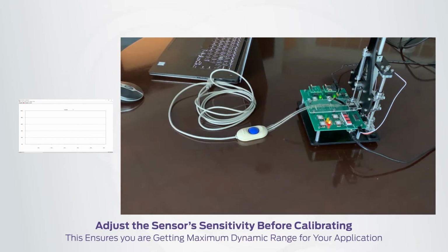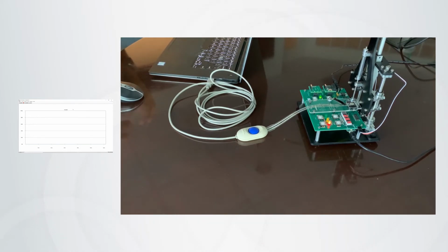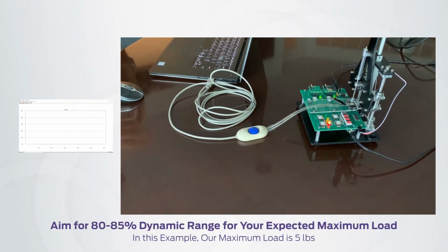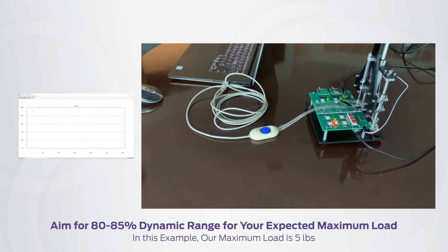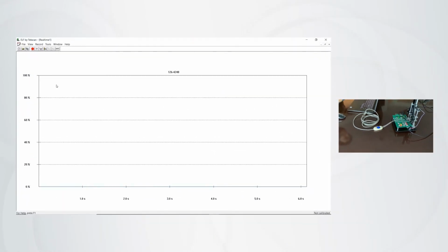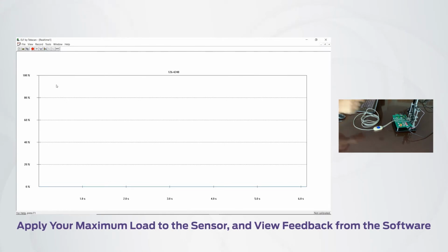Before we can calibrate, we want to adjust the sensitivity. Sensitivity adjustment ensures that the dynamic range of the electronics is properly aligned with the dynamic range of your force for the application. So in this case, our maximum load is going to be about 5 pounds. And generally what I recommend is setting your sensitivity so that you're getting about 80 to 85% output here on your real-time display at your maximum expected load. So we'll go ahead and apply 5 pounds to the sensor.